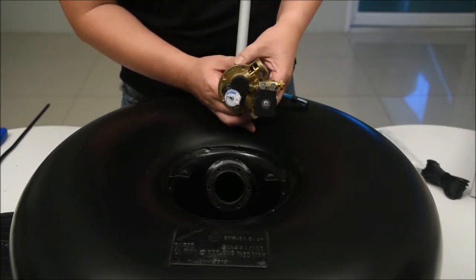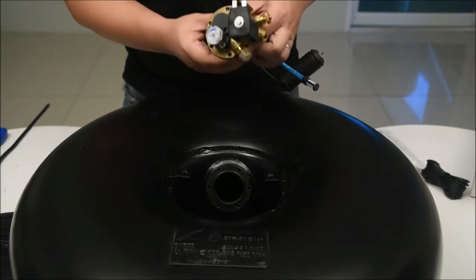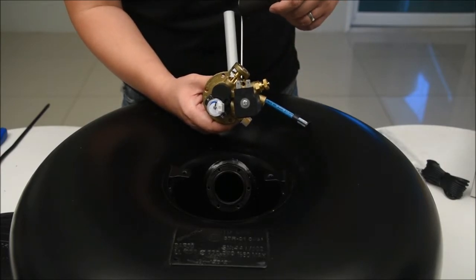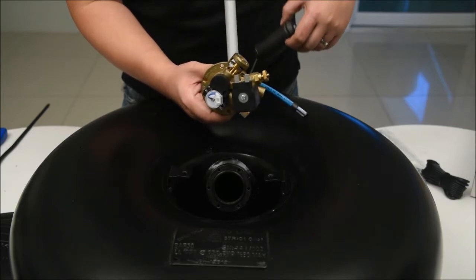Check the level indicator and floating level are compatible and working properly. When the floating arm moves up the level must show full capacity on the level sensor. When the floating arm goes down the level must show empty on the level sensor.